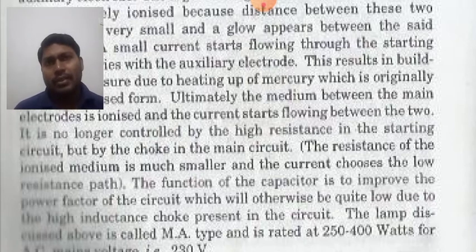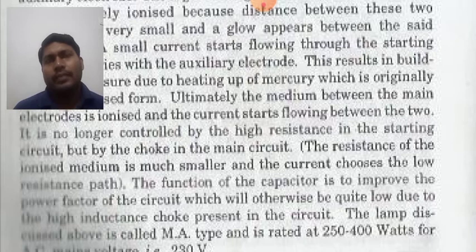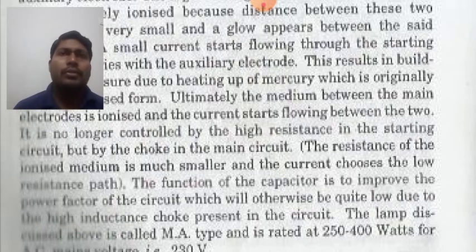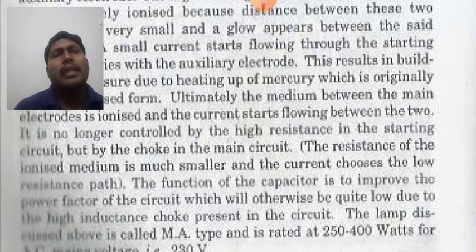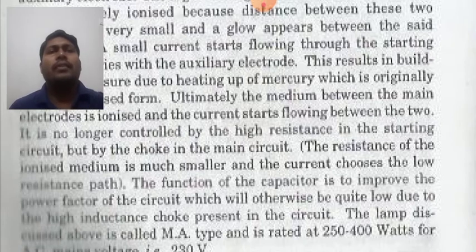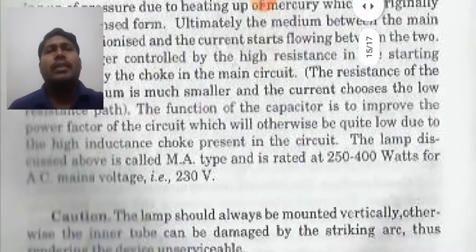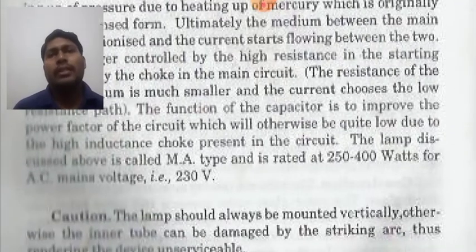The function of the capacitor is to improve the power factor of the circuit, which would otherwise be quite low due to the high inductance choke. The lamp is called MA type and is rated at 250 to 400 watts for a supply voltage of 230 volts.